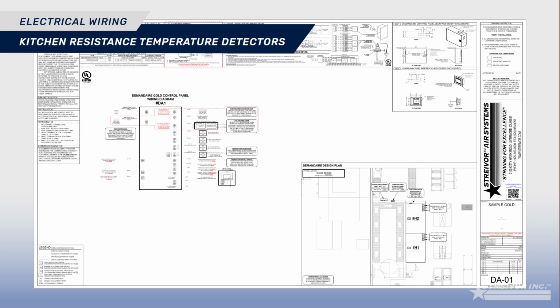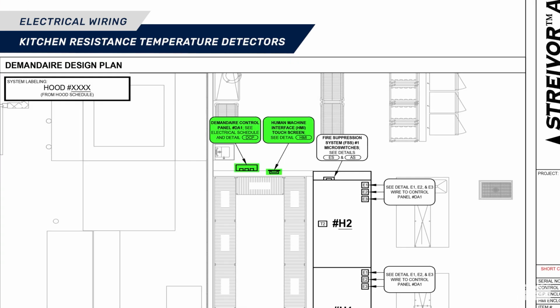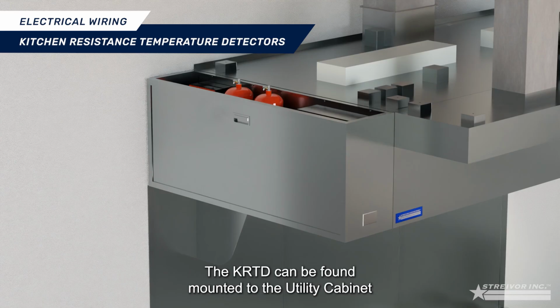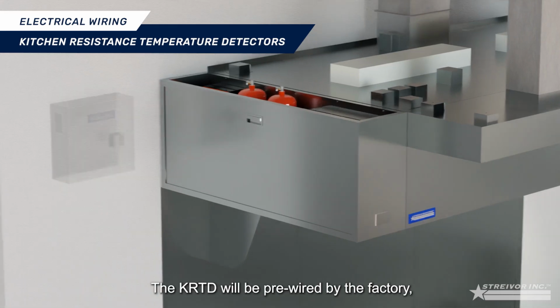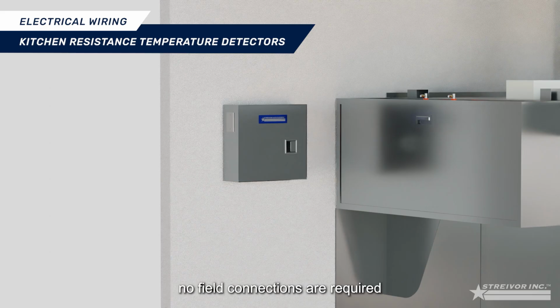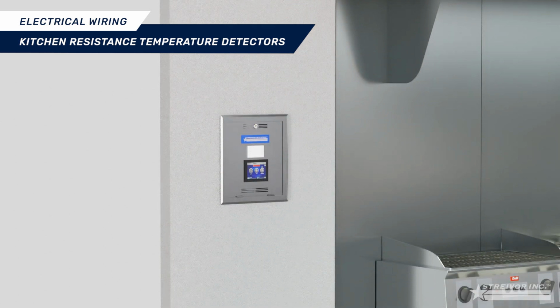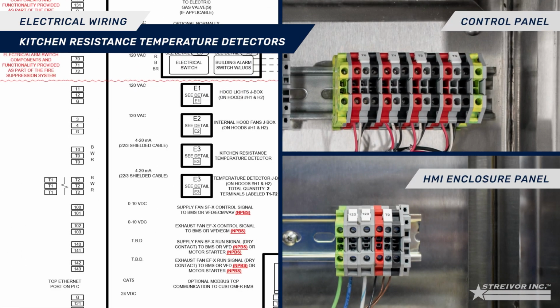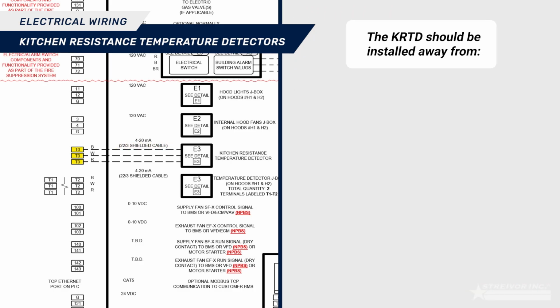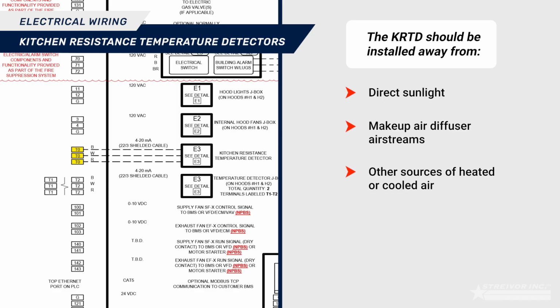Refer to the DemandAire drawings to verify the installation location for the kitchen resistance temperature detector, KRTD. If the KRTD is located on the utility cabinet or the control panel, it will be pre-wired in the factory. No field connections are required. If the KRTD is mounted on the HMI enclosure, connect the terminal blocks labeled T1-T2 in the control panel to the KRTD. Streivor recommends using UL-listed 22-gauge 3-stranded shielded cable. The KRTD should be installed away from direct sunlight, makeup air diffuser airstreams, and other sources of heated or cooled air.